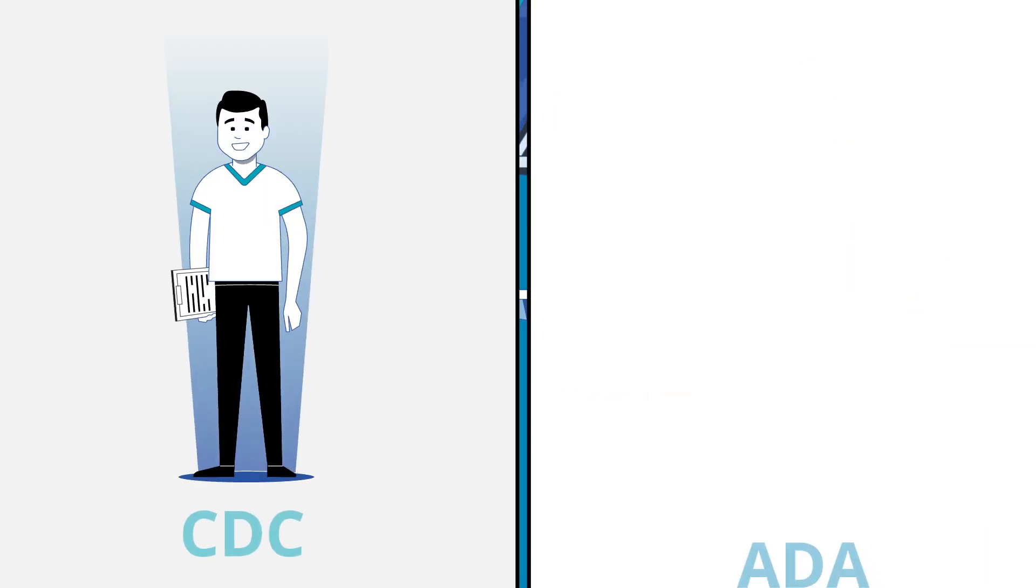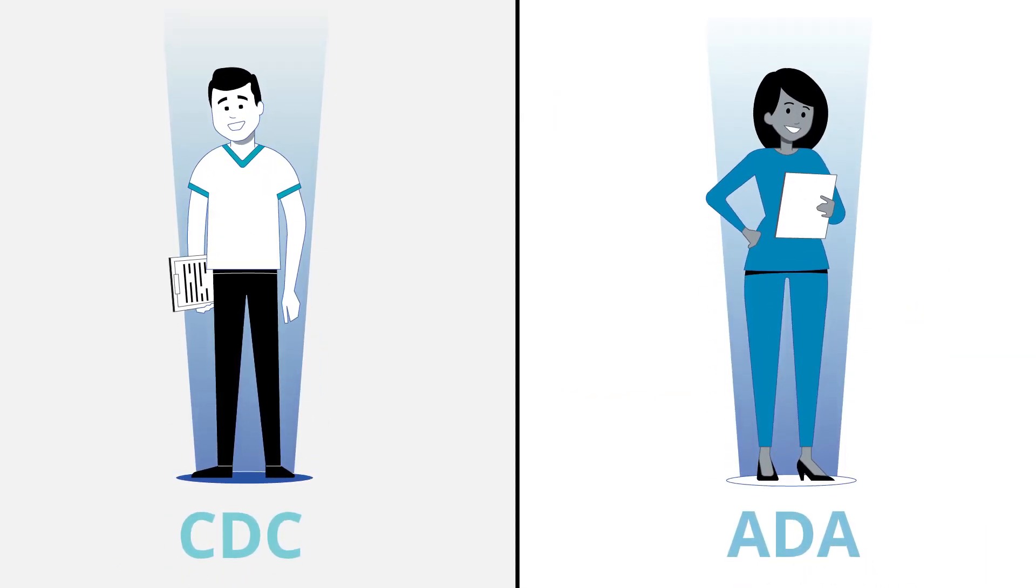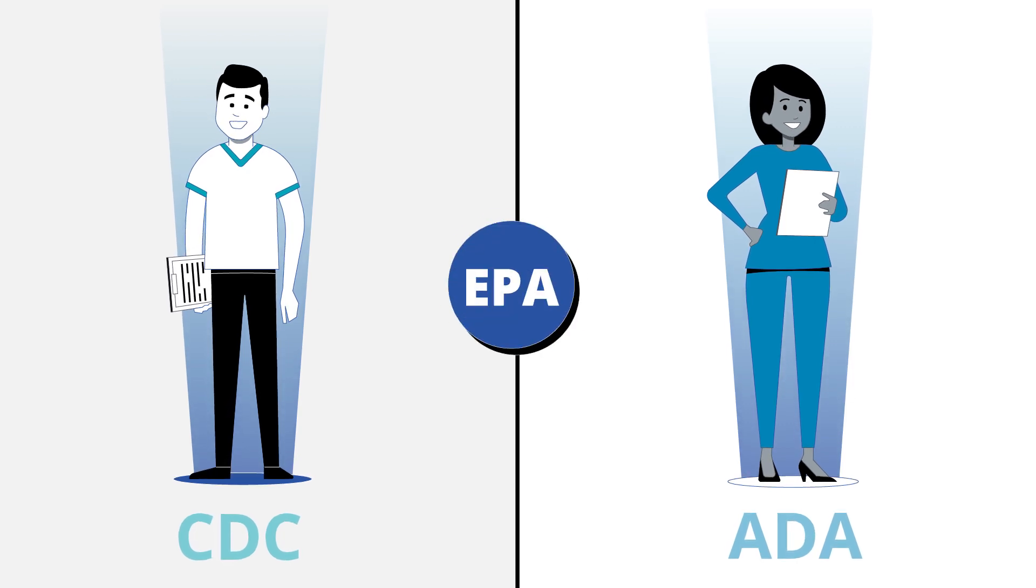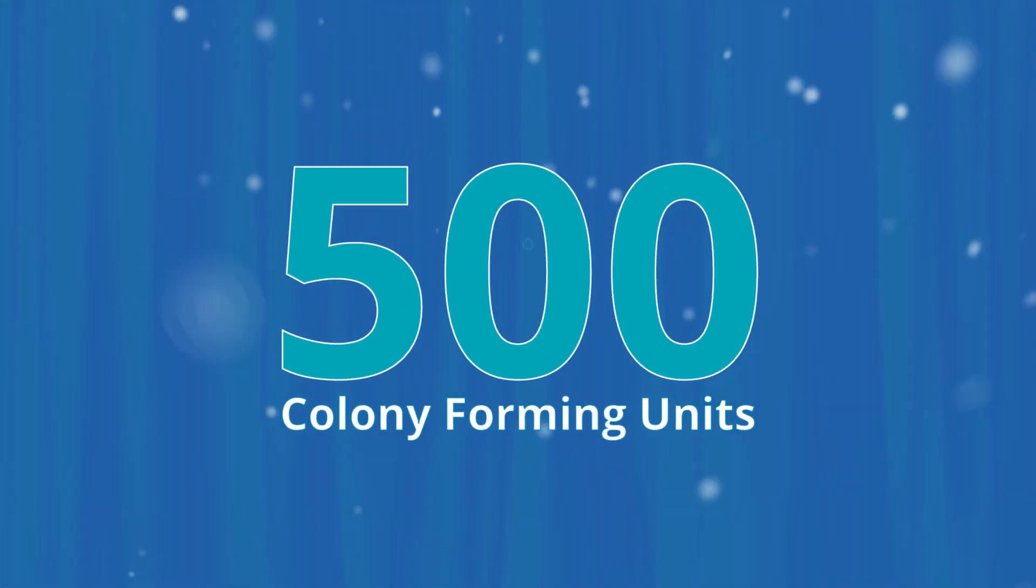Both the Centers for Disease Control and the American Dental Association recommend that water used in dental units meets EPA standards for safe drinking water by having a heterotrophic bacteria count of no more than 500 colony forming units per milliliter.